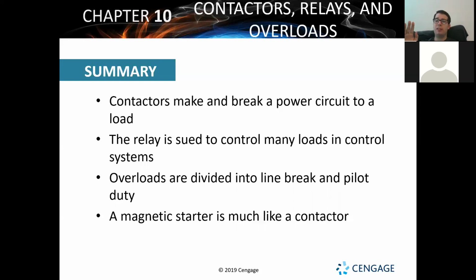Overloads are protective devices that are making sure that either temperature or amperage or whatever factor we're looking at is not exceeding safety as far as operation of the motor. And then the magnetic starter is going to be like a contactor with an overload. Those two basically had a baby together. I don't know. No. Okay. That was weird. So magnetic starter, again, it's going to be a contactor and an overload, basically comboed together.